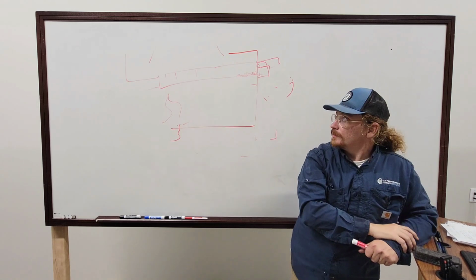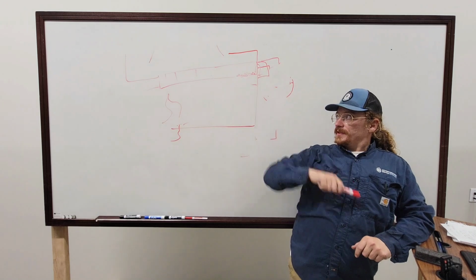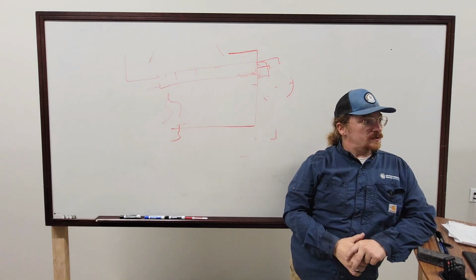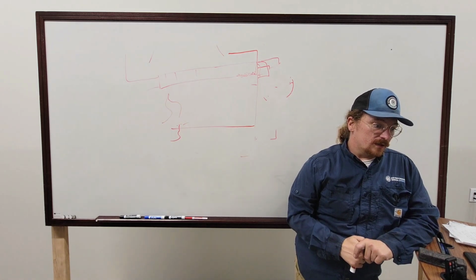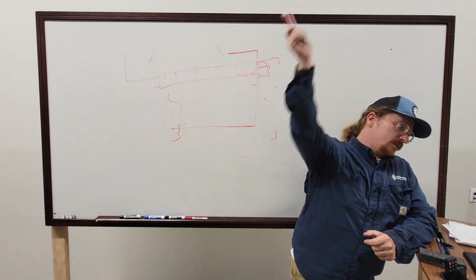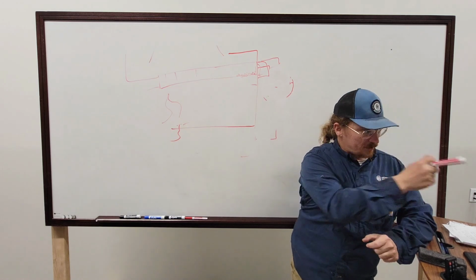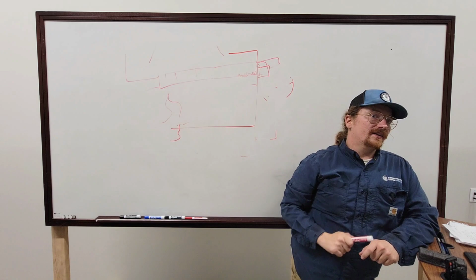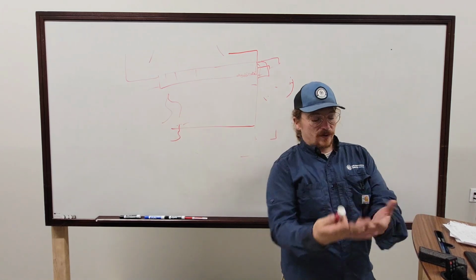That's the problem with a water tube like that: if you get any soot, the soot pretty much ruins it. If you have a natural gas boiler, you look under there, it has soot, it's pretty much replaced. I think that was the problem at one of my first adventures, because that's the one where we saw soot rolling out of the side of the building. And soot is an incredible insulator, and it will cause the problem that it's caused. They go hand in hand.